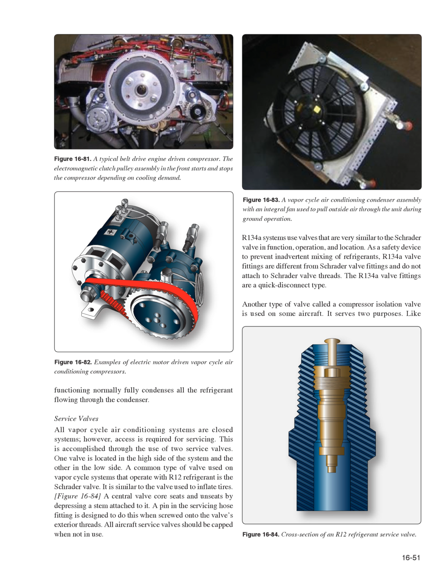A common type of valve used on vapor cycle systems that operate with R12 refrigerant is the Schrader valve. It is similar to the valve used to inflate tires. Figure 1684, a central valve core seats and unseats by depressing a stem attached to it. A pin in the servicing hose fitting is designed to do this when screwed onto the valve's exterior threads. All aircraft service valves should be capped when not in use.